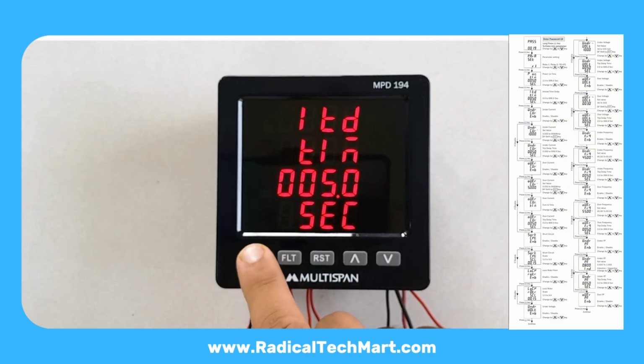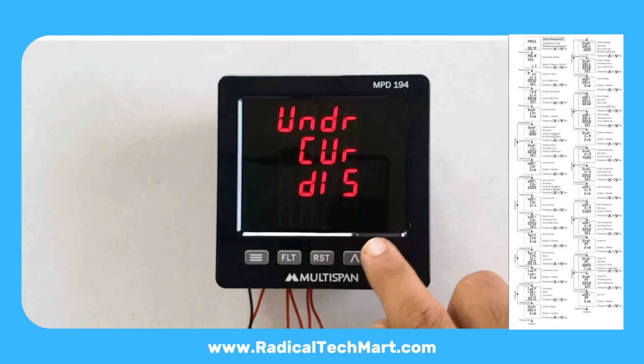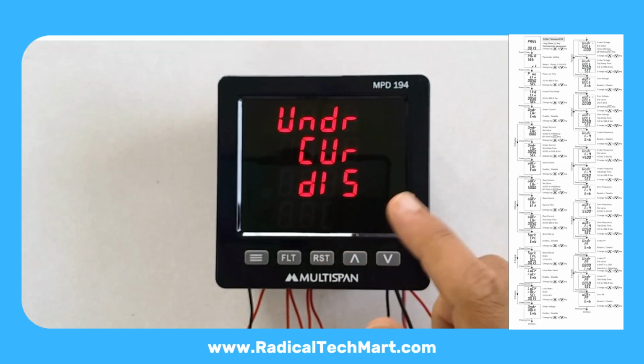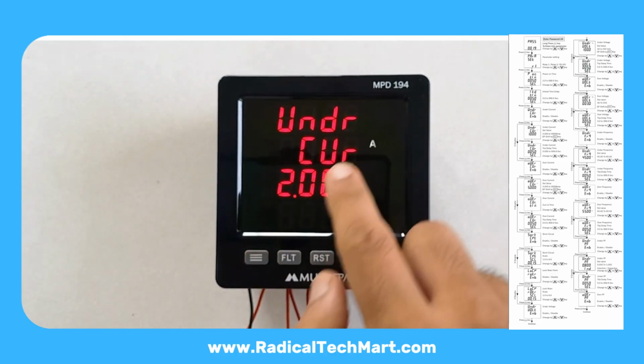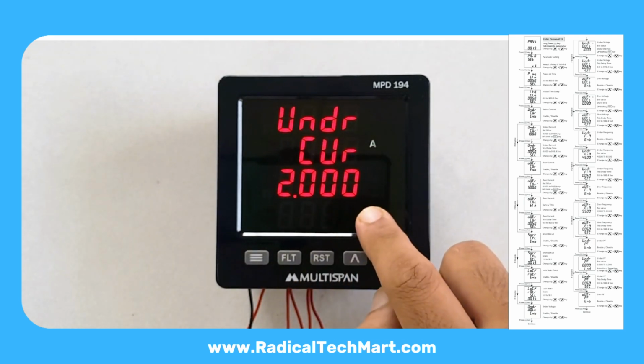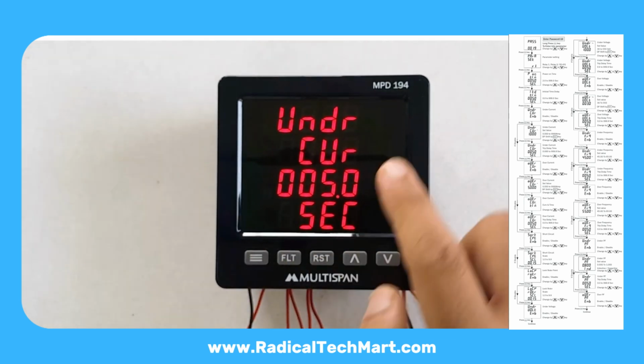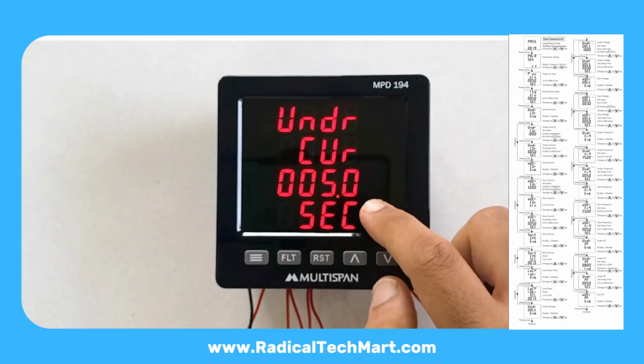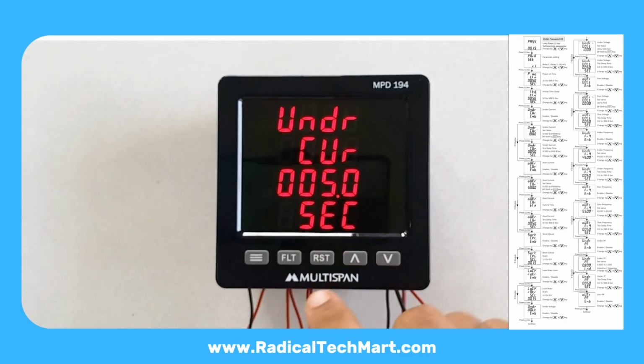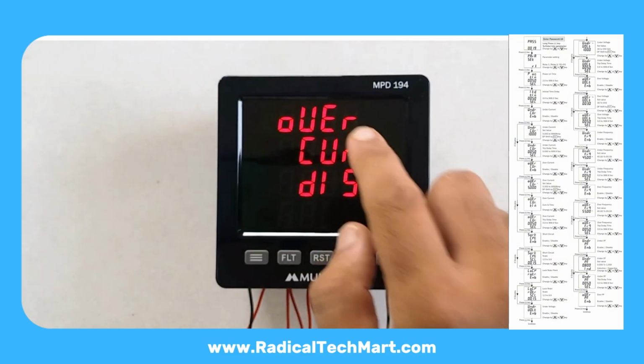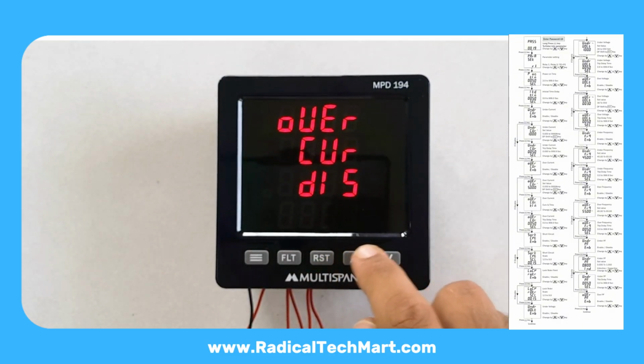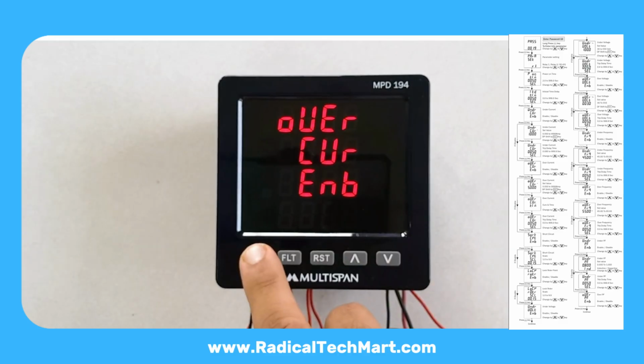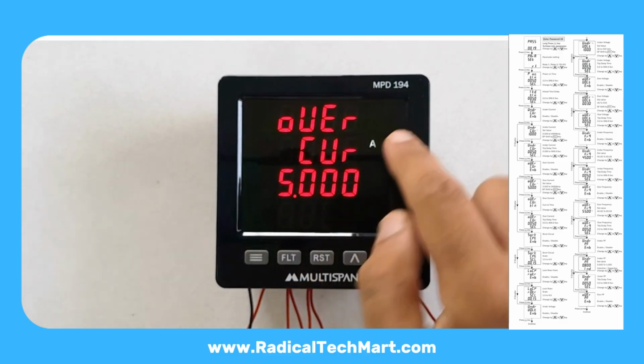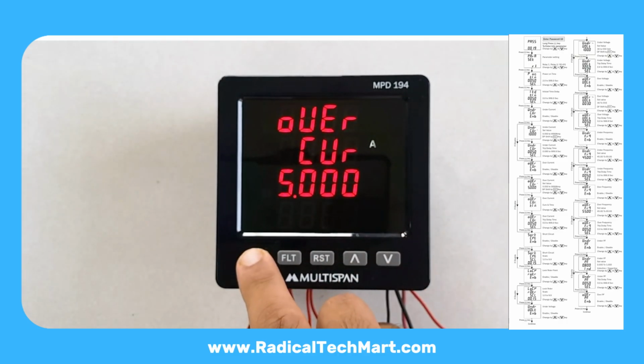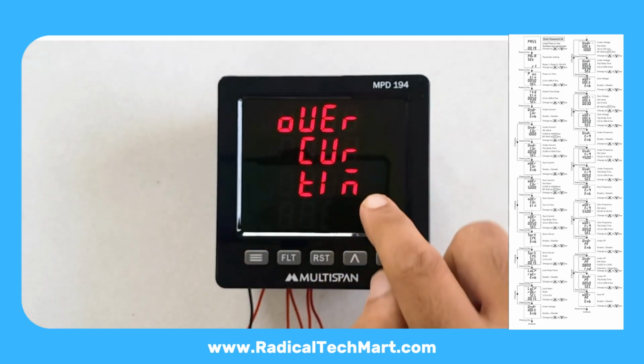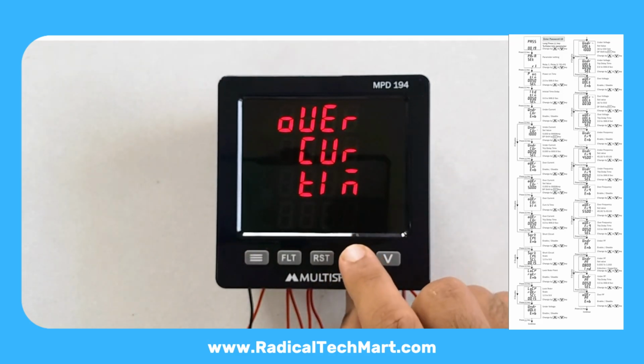Press set. Option to enable or disable undercurrent. If enabled, the next screen lets you set the undercurrent threshold in amperes, default 2 A. Next, undercurrent trip delay. Press set through these screens. Option to enable or disable overcurrent. Then set the overcurrent threshold in amperes. Next, choose overcurrent mode. Time-based or curve-based. We'll use time-based. Next, overcurrent trip delay time. Press set.